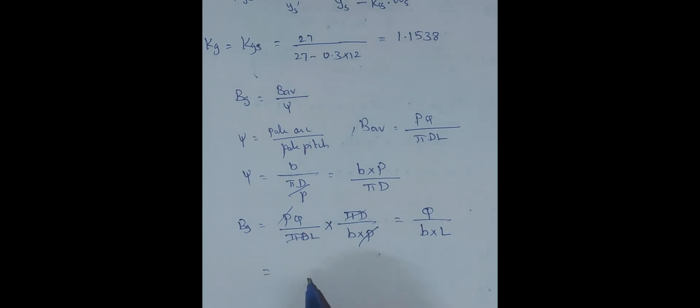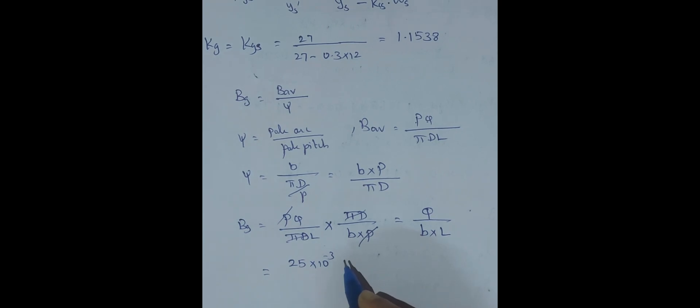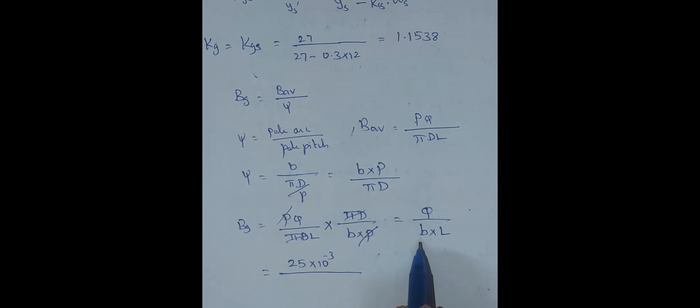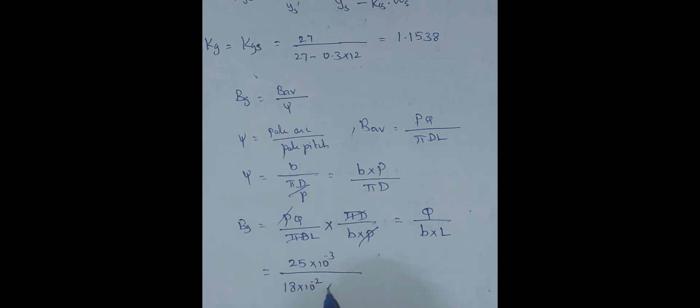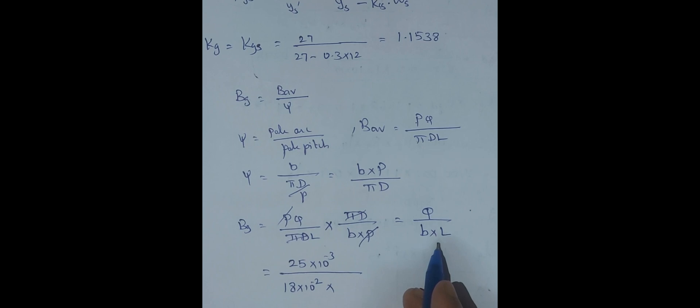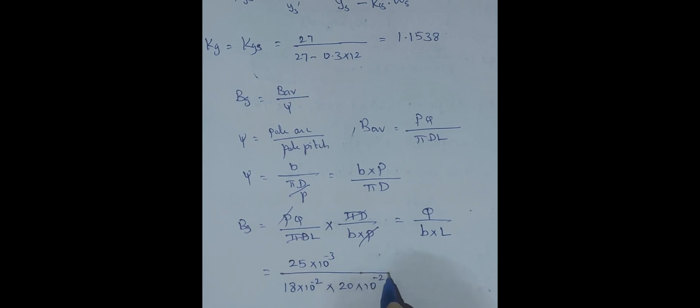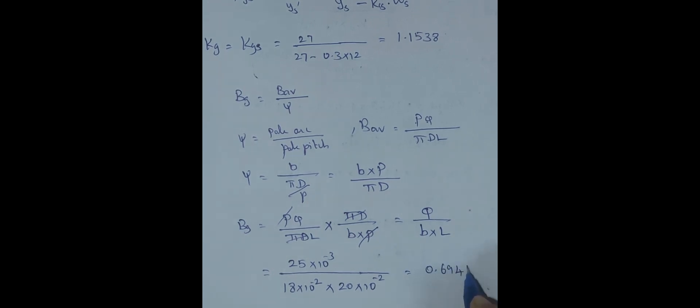Flux is given as 25 milliweber, so we will convert this into 25 into 10 power minus 3 weber. Pole arc is also given as 18 centimeter, so 18 into 10 power minus 2 meter. L is 20 centimeter, which is 20 into 10 power minus 2. After conversion and simplifying this, we'll get 0.6944 weber per meter square. So BG is found out.